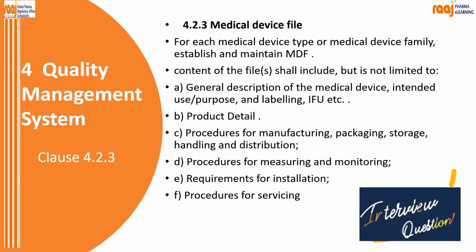Then 4.2.3 talks about the medical device file. If you recollect, last time we discussed this medical device file, right? What it comprises of. In the same way, we have to include this content: the general description of your medical device, your labeling, your IFU, product details, and procedures: how you manufacture, how you pack, how you store, how you handle, how you distribute, correct? Procedures for measuring, monitoring, requirements for installation, procedures for servicing.